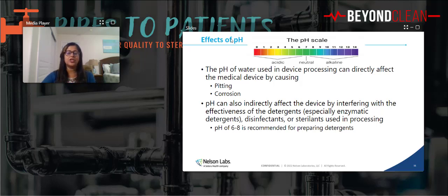When you change the pH of that scale by using the wrong water type, that validation is no longer valid at that point, right? So the processing instructions that you're following, I don't know if it's clean or not at this point, because I made sure that when I did my validation, it was at a pH of 6 to 8, which is where most neutral pH detergents are. So that's why it's very important that you understand that pH does play a major role in cleaning validations, because it can alter the pH of the detergent that you're preparing as well.